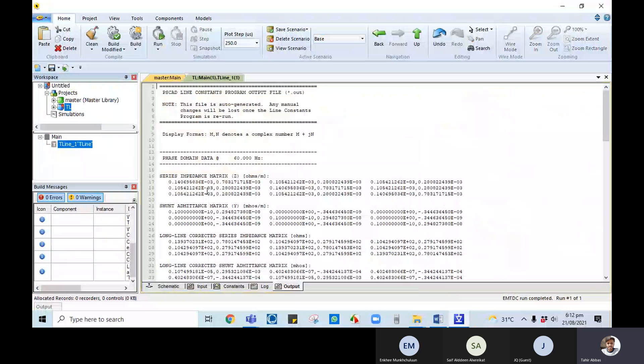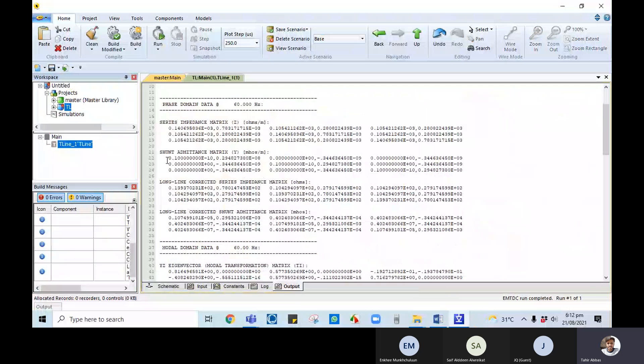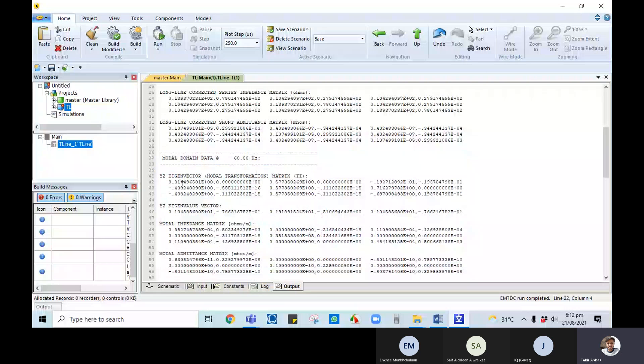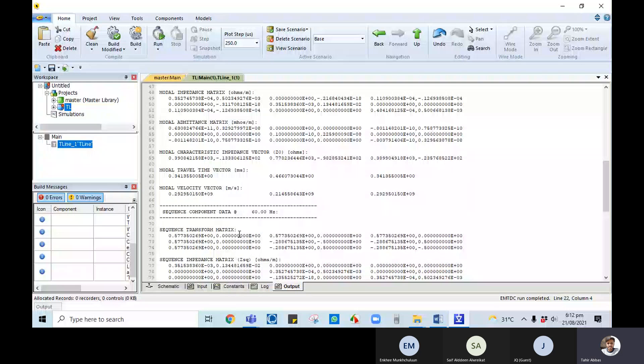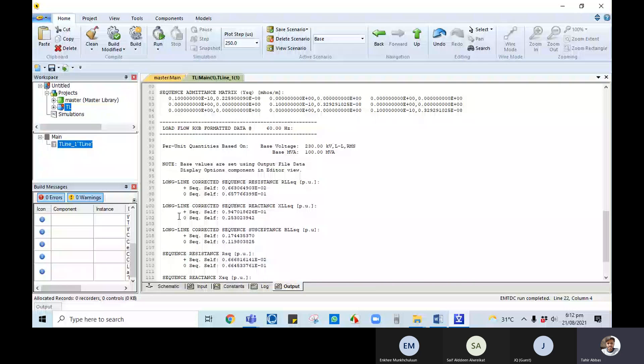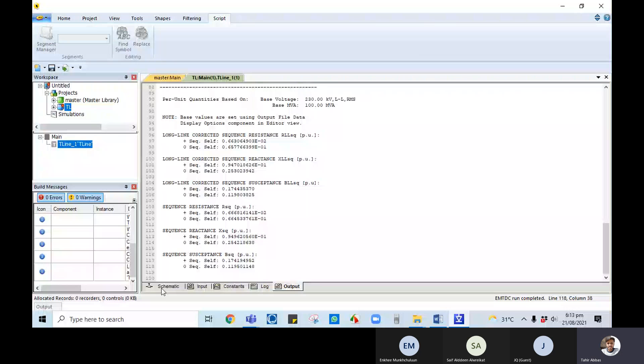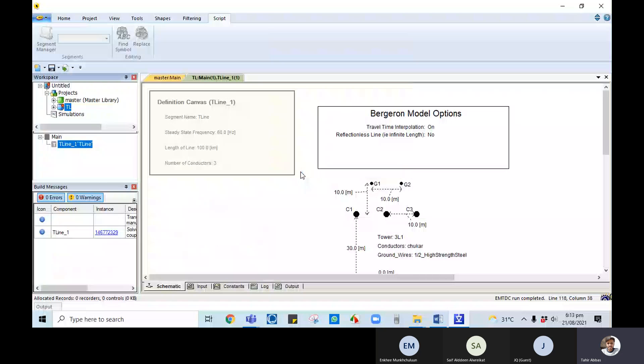After editing the definition, you will see the output including the impedance matrix, shunt admittance matrix, long-line impedance matrix, eigenvalues, modal transformation matrix, and sequence component data — positive sequence matrix and others. Power per unit line long-line corrected positive sequence in per-unit, shunt admittance, and resistance are all available here. The other way is to go to the schematic view and click Solve Constants.